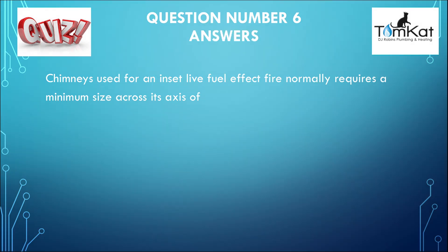Now the answer for question number six: chimneys used for an inset live fuel effect fire normally requires a minimum size across its axes of? The answer is A — 125 millimetres. That was the answer to question number six.